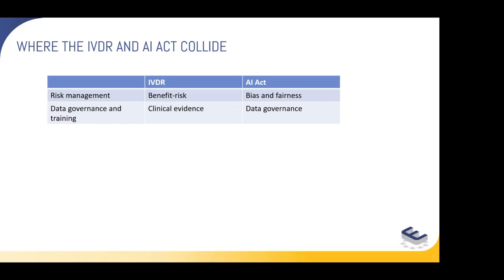The AI Act looks at this through a slightly different lens. Whilst the IVDR is outcome focused, the AI Act is process focused. The AI Act tells us that the training, validation, and testing data sets need to be relevant. They need to be representative of the population that the algorithm will be used on, and the algorithm also needs to be free of errors, which means that a sufficient amount of validation needs to go into the development of these algorithms before they can be released. So this needs to take demographic variations into account, as well as any bias detection by the algorithm or from the algorithm.